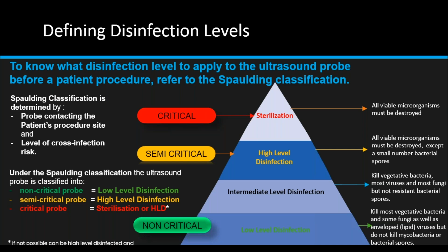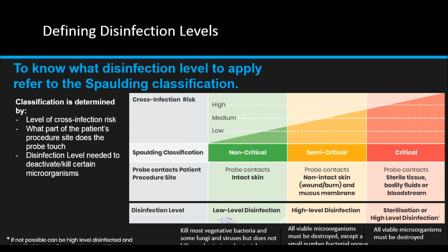Now, low-level disinfection will kill most vegetative bacteria and some fungi, but will not kill mycobacteria or spores or non-enveloped viruses. Intermediate disinfection will be between that and high-level disinfection. Again, high-level disinfection will eliminate everything except very high numbers of spores, may not eliminate all the spores. Sterilization means that all viable microorganisms have been destroyed. So again, this is the basis that's widely accepted worldwide, including in the U.S. by the Centers for Disease Control, that determines how we disinfect an object. And again, you can see here just the same thing showed differently. Non-critical, a probe contacting intact skin, and semi-critical probe contacts non-intact skin, but could also contact mucous membranes or non-intact skin, and then critical would be something that's entering body tissue, like you're doing an ultrasound of the liver during surgery.